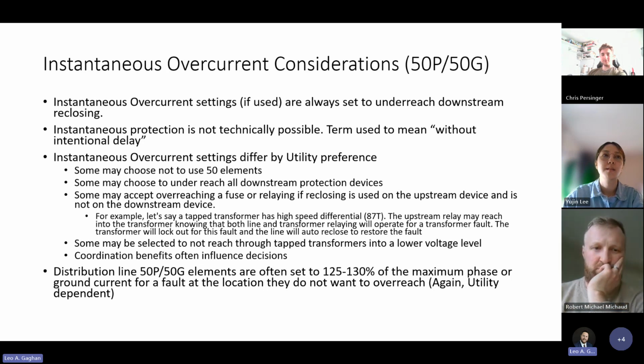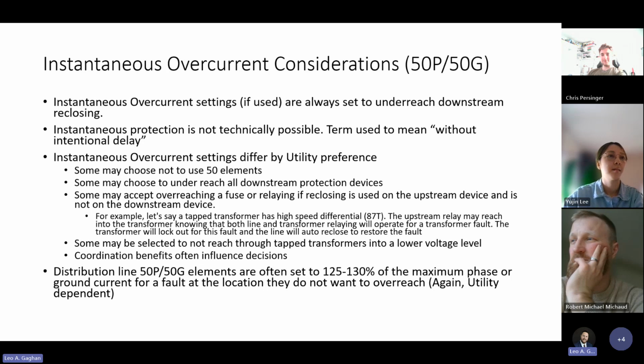We'll start with instantaneous overcurrent. All right, there's never anything instantaneous, but we'll call it without intentional delay. We always have to think, it takes the relay a little bit of time to detect it. It's usually about a cycle. It takes contacts on the relay time to actually close, takes the breaker time to open. So nothing's ever instantaneous.